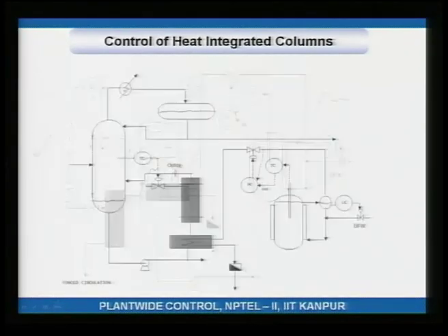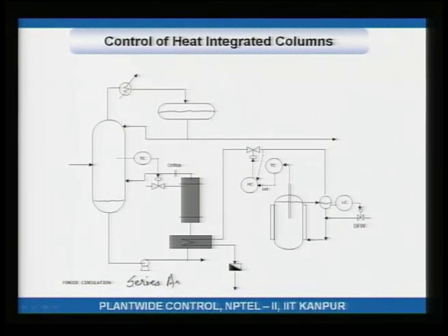A design solution is a series arrangement. In this case, notice what happens. The way the two reboilers are arranged, they are in series. In this series arrangement, this reboiler takes steam from the reaction section, and there is some boil up that is created because of that, which is fed to the auxiliary reboiler, which is taking its own steam, and that creates further boil up.